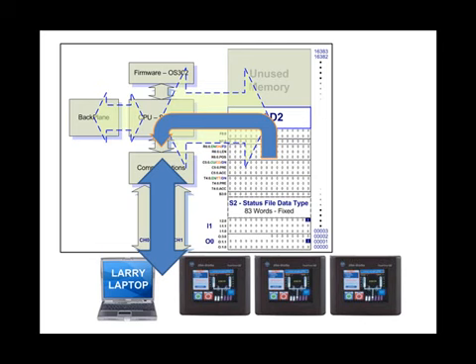In this industry, we refer to this type of system as having 'naked data.' That means that while you are intently troubleshooting a machine, a board operator can be walking by poking buttons at random and changing the data in the data table. The characteristic of this type of controller is that you can plug another PLC into one of these COM ports and, by means of a message instruction, read anything from this memory and write anywhere into this memory — without this controller needing to give the other controller permission.